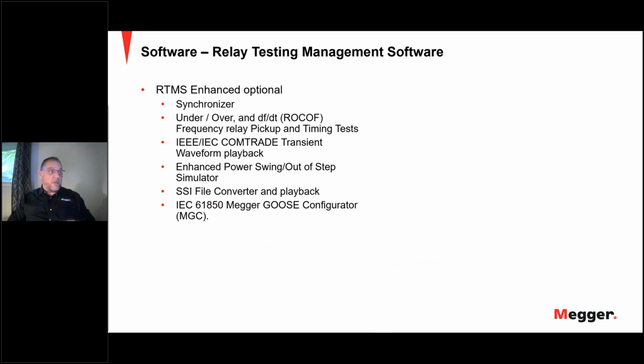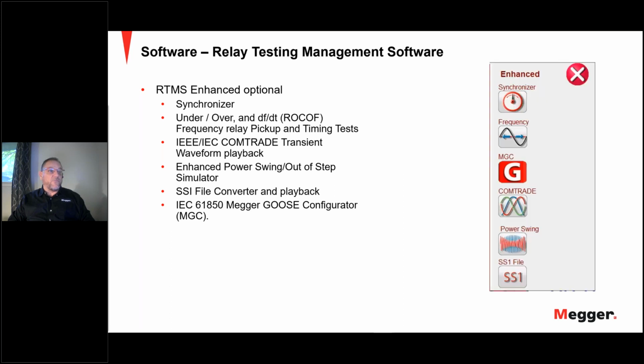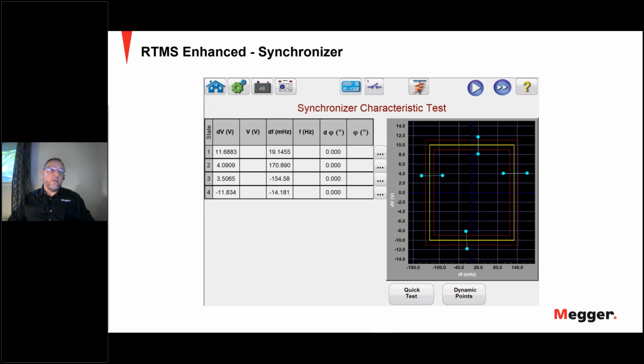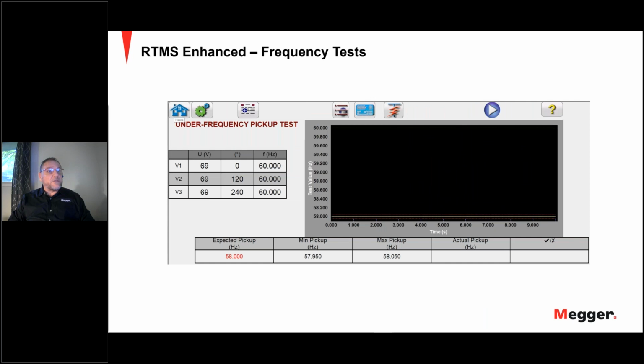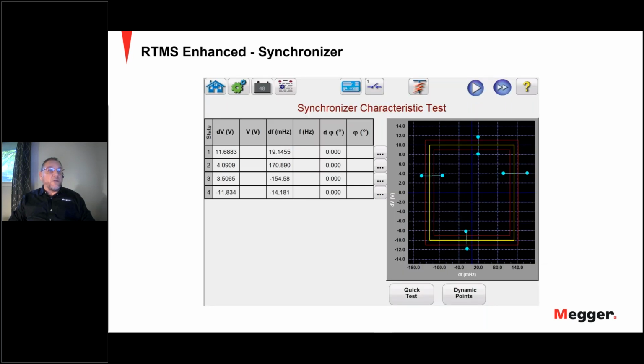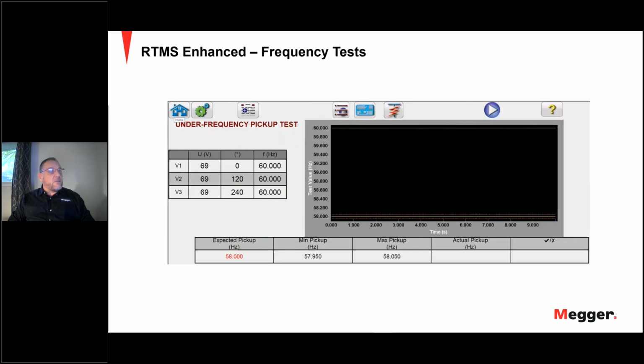Okay, then we move on to the enhanced version of the software, which includes the synchronizer, under-over, and rate of change for frequency relays, IEC and IEEE COMTRADE transient waveform playback, power swing, SS1 file converter, and the IEC 61850 Megger GOOSE Configurator. So very quickly, first the synchronizer, and then the frequency test. You can perform the under frequency, over frequency, and rate of change of frequency tests.